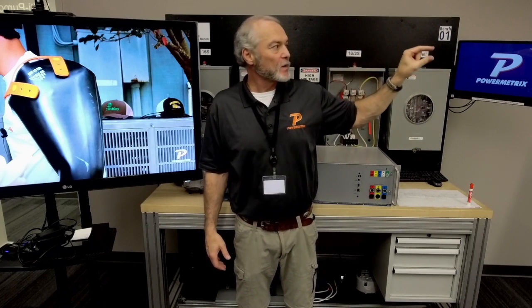The class double-aught gloves are 500 volt, and the class aught gloves are 1,000 volt. You may call it differently where you are, but we look at those as low voltage or distribution gloves, since you're just talking up to 1,000 volts. When you get to the class 1 and 2, the 1 is rated for 7,500 volts and the 2 is rated for 17,000 volts. Those are considered high voltage gloves for us.